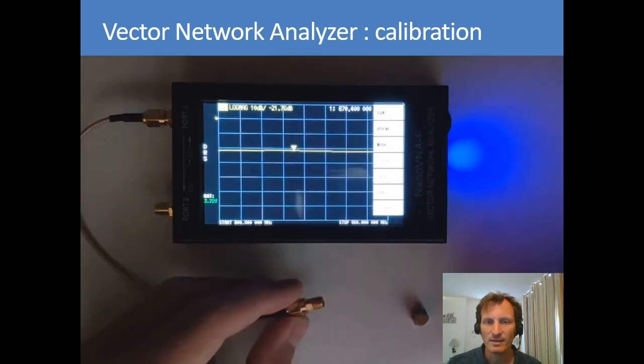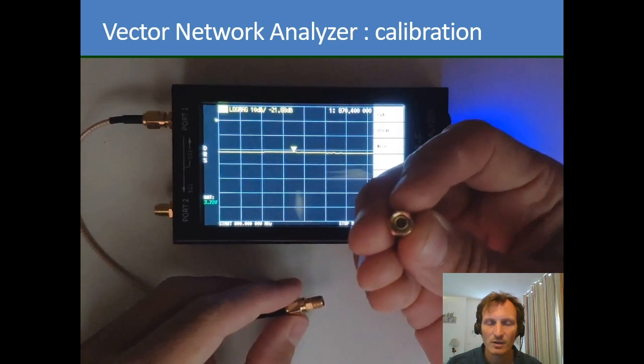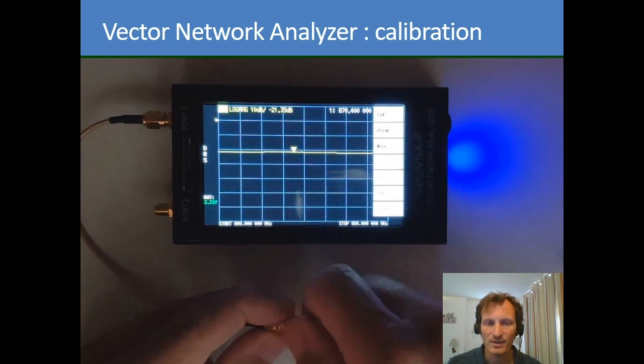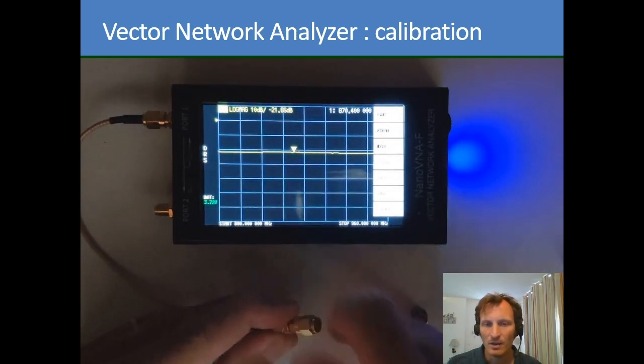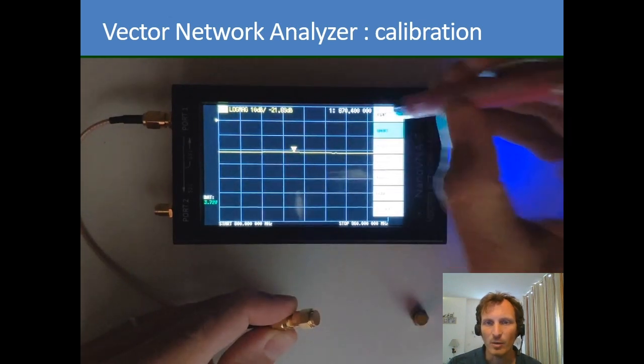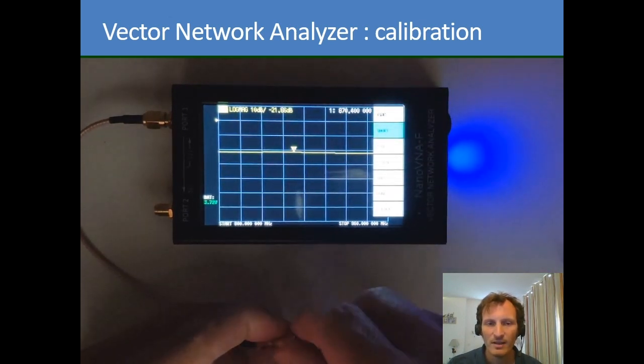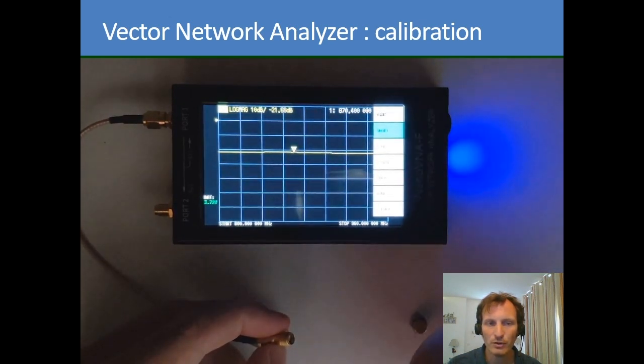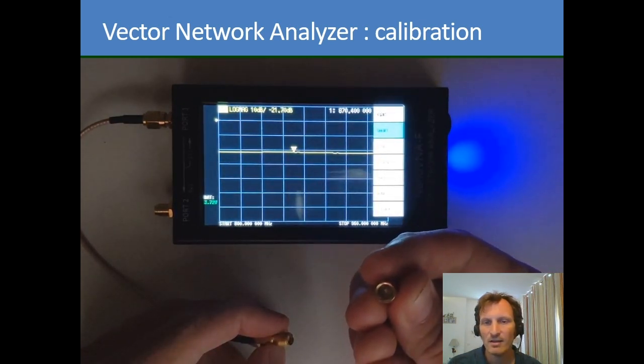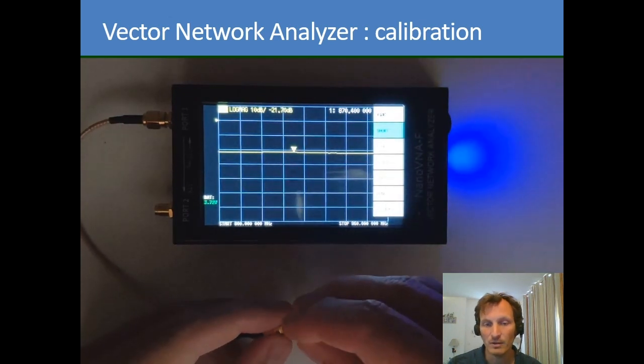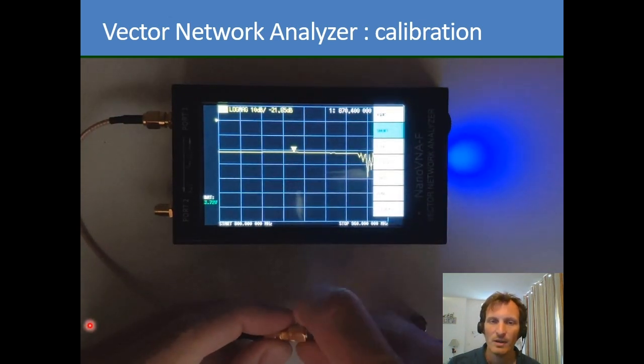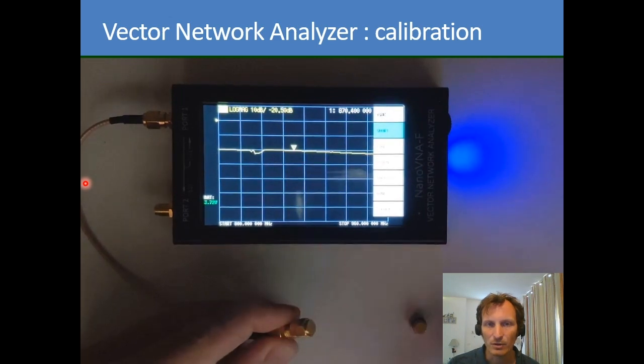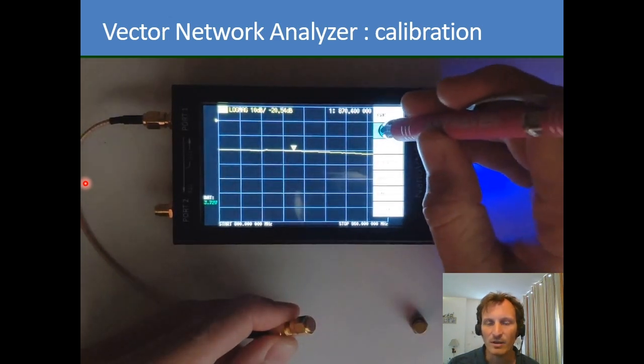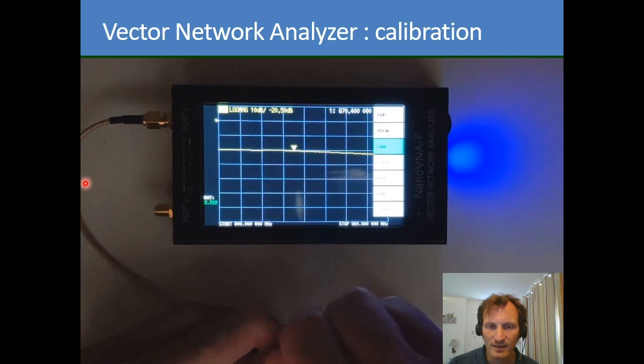So then we start the calibration. We are going to start first with the open circuit. So you connect the open circuit and click on open circuit. Then we are going to remove the open circuit and put the short. You can easily find the short because you see that there is a connection between the signal and the ground. So we connect it, and again we click on short, and the last load that we need to connect is the 50 ohm.